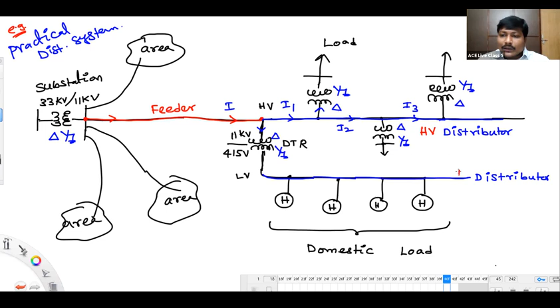See what we call this portion. Can anybody tell me what we call this one? Can we call this also a distributor? Yes, definitely, because current is changing with respect to length, and this can also be called a distributor. But voltage levels are different. The upper distributor is operating at a voltage level of 11 kV. You can call it an HV distributor. The lower distributor is operating at a low level of 415 volts. You can call it an LV distributor. HV distributor and LV distributor, or you can say primary and secondary distributor. The bottom one is the secondary, the top one is the primary. Like that you can discriminate these two.